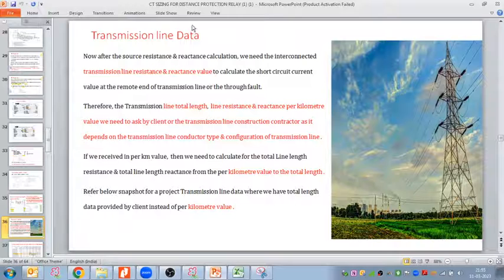So after the source resistance and source reactance calculations, the ultimate motto of the resistance and impedance calculations, Bharat, is the through fault current calculation. For that, you need the impedance till the last point of your transmission line. Till the substation we first calculate the resistance and reactance, and to that we add the transmission line resistance and reactance, and after that we calculate the impedance at the last protected point. Once you know the impedance and the voltage, you can find out the fault current. This is the purpose why we are calculating the source resistance and the source impedance.